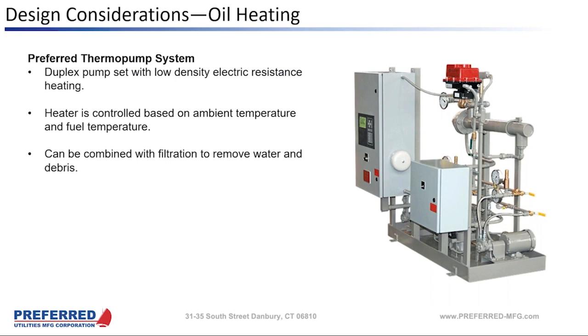And the reason being is that this can address temperature issues in any part of the system. The suction stub or immersion heater really is limited to its extreme location. But whether you're using the outdoor air temperature sensor or an RTD in the main tank, I mean, we can place an RTD really anywhere in the system, if you want it up in a day tank, and have this run.